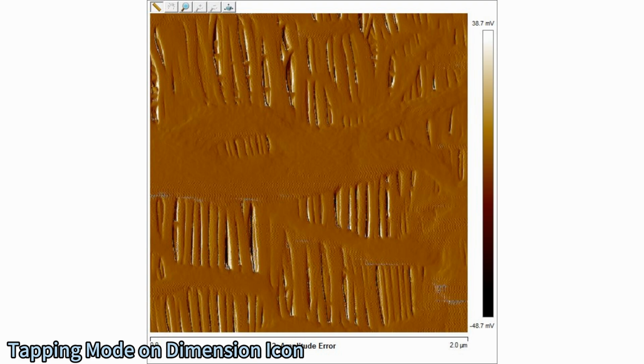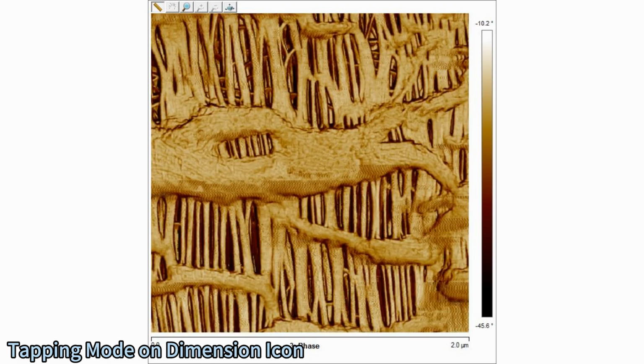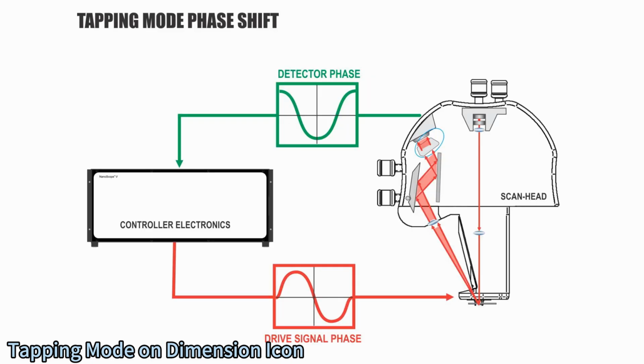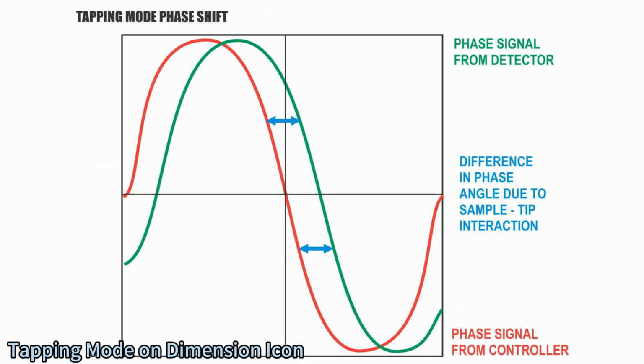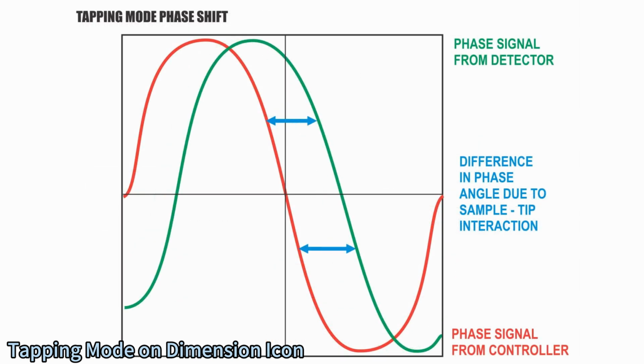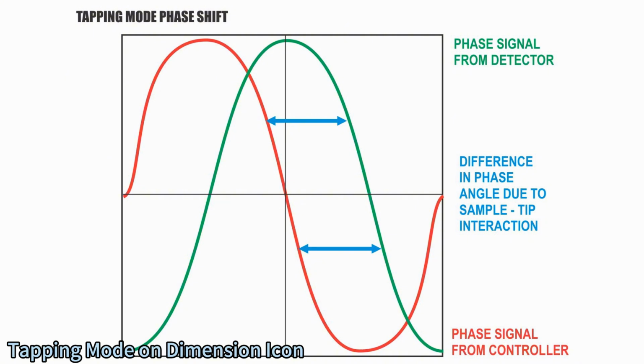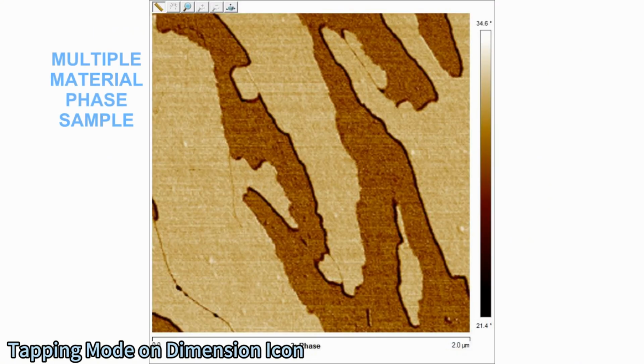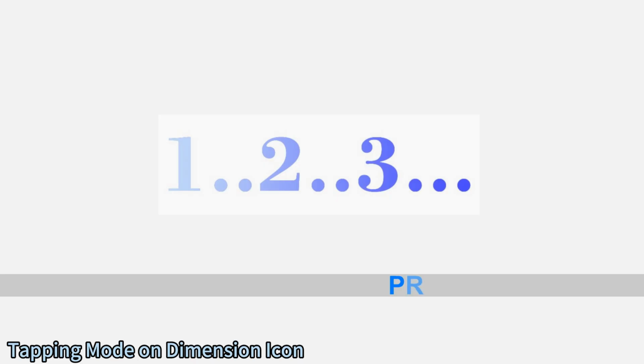Additional data can be derived from the tapping amplitude error and phase channels. Phase images are derived from the difference between the phase angle of the signal that drives the probe and the phase angle of the resulting signal from the photodetector. The shift in the phase is influenced by the forces between the sample and the resonating probe tip. Different materials can produce different amounts of phase shift.